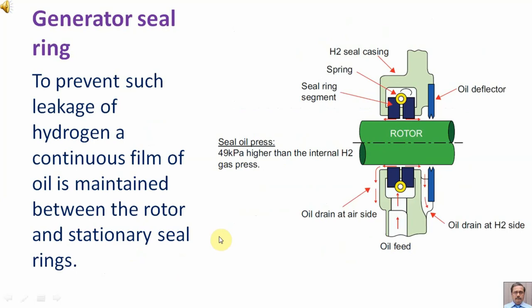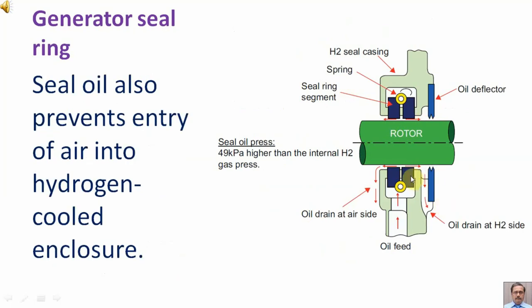To prevent such leakage of hydrogen, a continuous film of oil is maintained between the rotor and stationary seal rings. Seal oil also prevents the entry of air into the hydrogen-cooled enclosure.